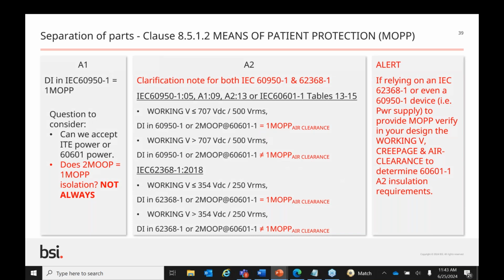So you'll want to take a look at Note 1 of 8.5.1.2 related to means of patient protection that are very important pieces of information, which the A2 box in this slide shows the detail of Note 1, just written differently than Note 1 is written. It's a little easier to read probably. If you were looking to take a power supply that's either 62368-1 or 60950-1 evaluated and understand the important voltage measurements that were made across an isolation barrier or a set of barriers, and how that working voltage measurement pertains to 601 and its ability then to serve as a means of patient protection, this is pretty critical.